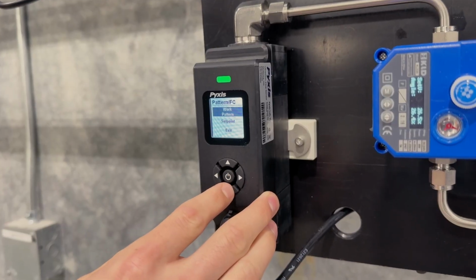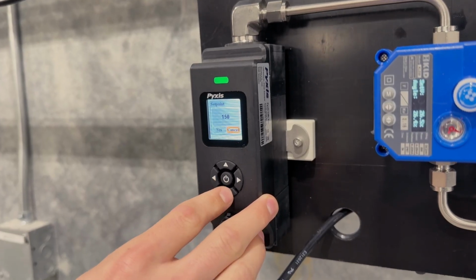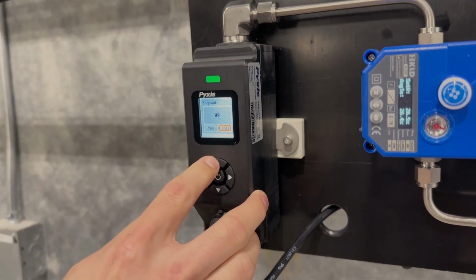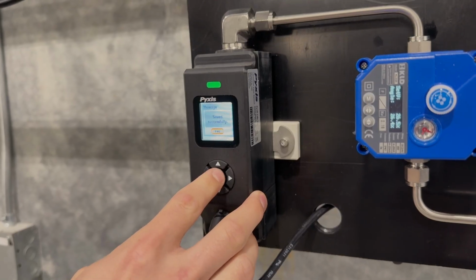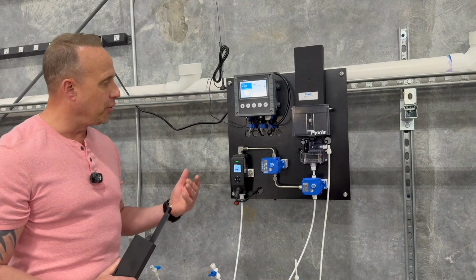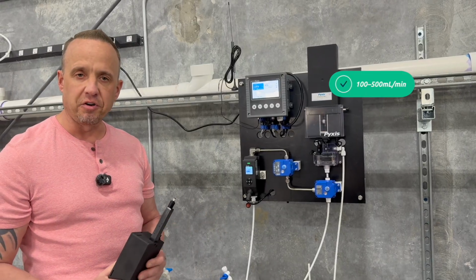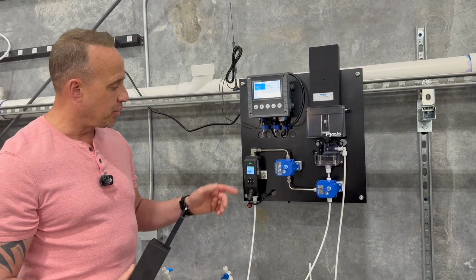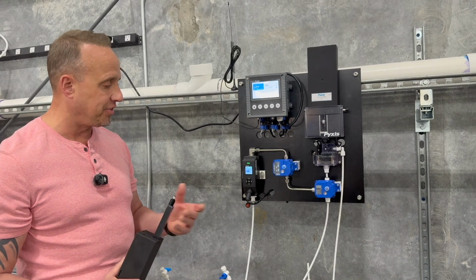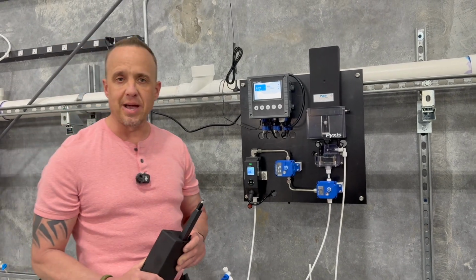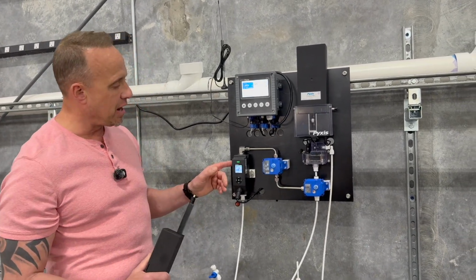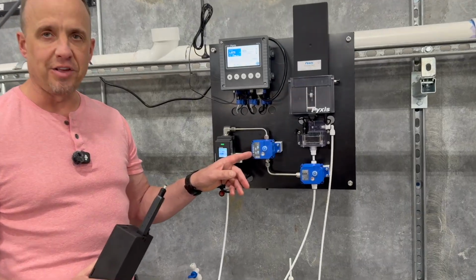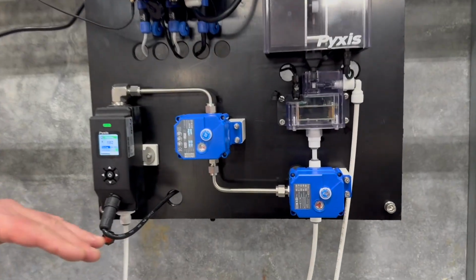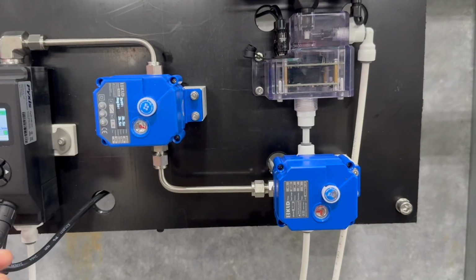sensor. That flow sensor can be programmed into a control mode, and when in control mode, the user can define the flow rate set point through the analyzer. The recommended flow rate set point for this analyzer platform is between 100 and 500 milliliters per minute.